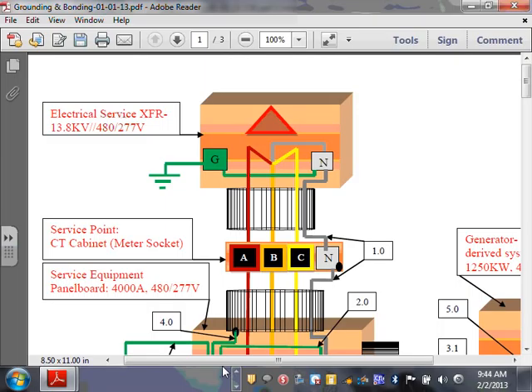And that transformer typically is Y grounded, like you can see. And you have your neutral and the ground bar. They're bonded together, and they drive a ground rod typically right by the transformer the utility has, right? Do you guys see it differently? And we, as contractors, have no control over this system. We have no interface with it. We don't deal with it, right? Do you guys go there and ground the transformer for Xcel? We don't really ground the transformer for Xcel, be it a pole-mounted transformer or a pad-mounted transformer. We don't get into that system.